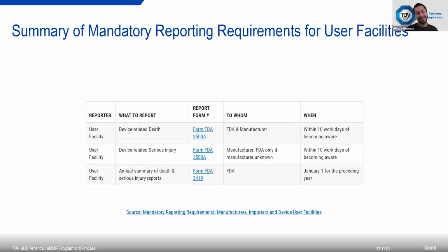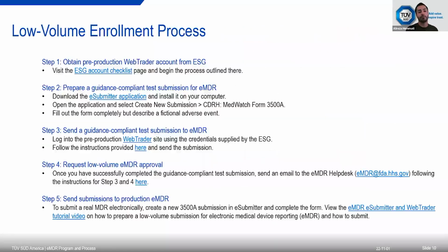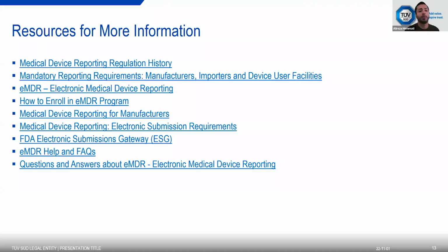The final rule stated here, the eMDR one, is specifically related to e-submission, but the MDR reportable guidance, I have it here, mandatory reporting requirements, manufacturers, importers, and device user facilities. This guidance document should specifically mention whether that's a requirement or not. I personally suggest having that document at hand, release it in your quality management system, even if FDA is not requiring you to send it in.